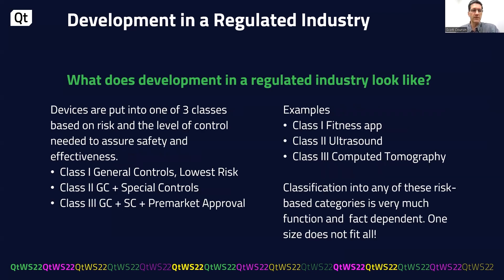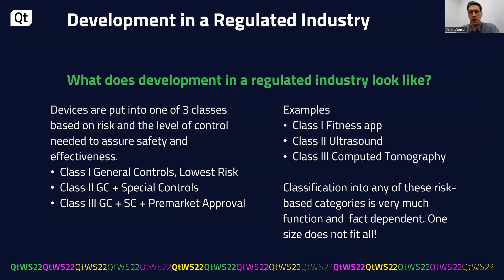The regulations applied depend on the type of product being offered in terms of risk, intended use, and the indications for use. Indications are things such as labeling or verbal communications from the manufacturer. Some examples: Class 1 would be something like a fitness app on your smartphone — it has a low amount of risk and the lowest amount of regulation. Class 2 would be something like ultrasound. Class 3 is a little riskier, something like computed tomography or CT, due to the extra radiation. Classification of these devices depends on the requirements for each class, and of course there are exceptions to these rules.